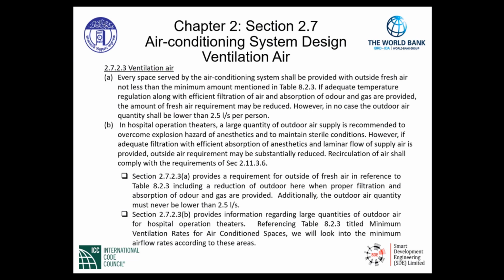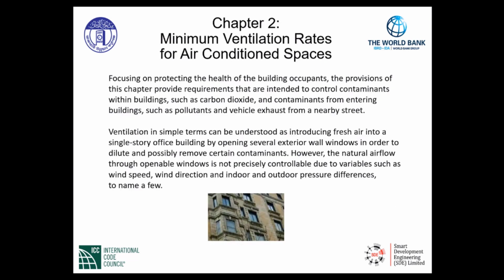Referencing Table 8.2.3 titled Minimum Ventilation Rates for Air-Conditioned Spaces, we will look into the minimum airflow rates according to these areas. Focusing on protecting the health of the building occupants, the provisions of this chapter provide requirements that are intended to control contaminants within buildings, such as carbon dioxide, and contaminants from entering buildings, such as pollutants, vehicle exhaust from a nearby street, just to name a few. Ventilation in simple terms can be understood as introducing fresh air into a single-story office building by opening several exterior wall windows in order to dilute and possibly remove certain contaminants. That is what we call natural ventilation.